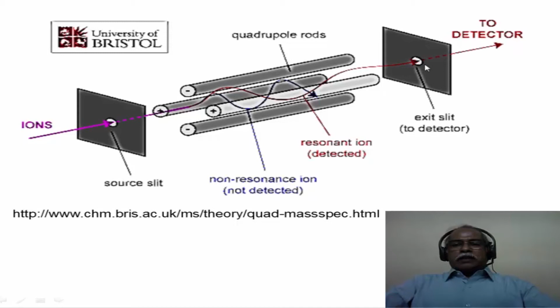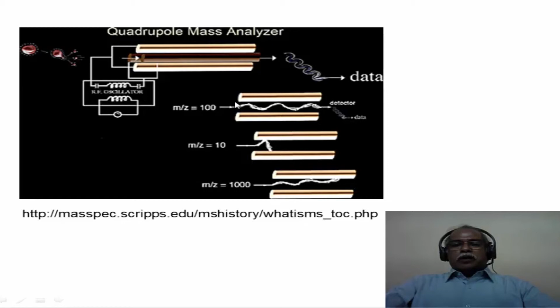For example, this is a quadrupolar analyzer. In this particular case there are 3 ions, M/Z of 10, M/Z of 1000 and M/Z of 100. The applied voltage is such that only the M/Z value of 100 passes through. This is called the resonant ion, which passes through the quadrupole analyzer to the detector. On the other hand, the smaller ion, which has the M/Z value of 10, has a non-resonant nature, and it hits the walls of the quadrupole analyzer at a very early stage itself, whereas M/Z 1000 travels a certain distance and finally hits the walls of the quadrupole analyzer before it comes out. So only a particular M/Z value for a given voltage will pass through the quadrupolar analyzer, and that is the basic principle of the quadrupolar analyzer in this case.